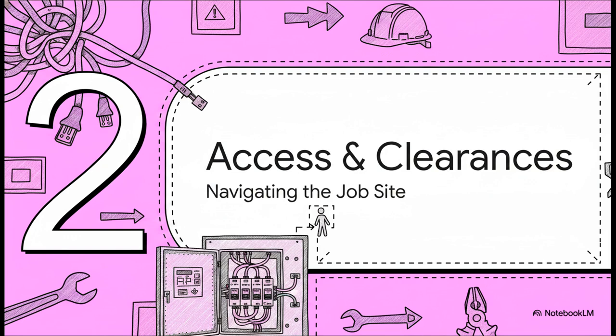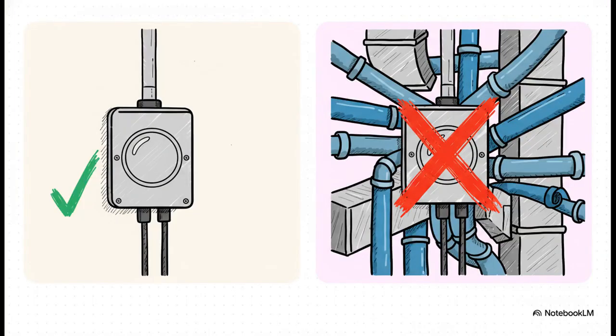Moving on to Section 2, Access and Clearances, navigating the job site. The code makes a really sharp distinction between the word accessible when talking about equipment versus wiring methods. The 2023 update adds a major clarification: if wiring is blocked or made inaccessible by building piping, ductwork, or other mechanical systems, it is strictly not considered accessible anymore. It makes sense, right? You can't just assume some poor guy down the line is going to disassemble a building's plumbing just to reach an electrical junction box. This update prevents some totally impossible and frankly dangerous maintenance scenarios.